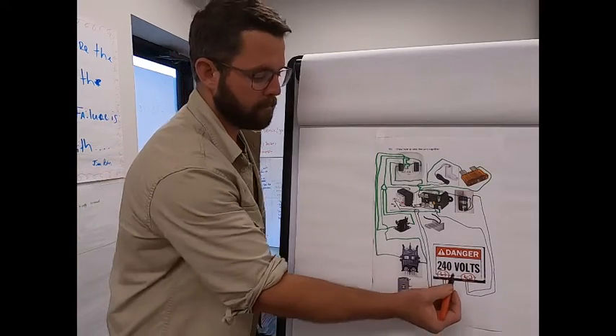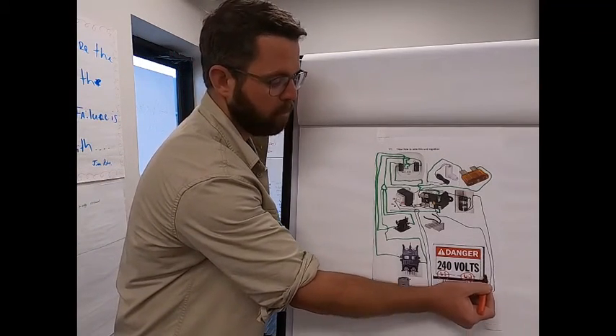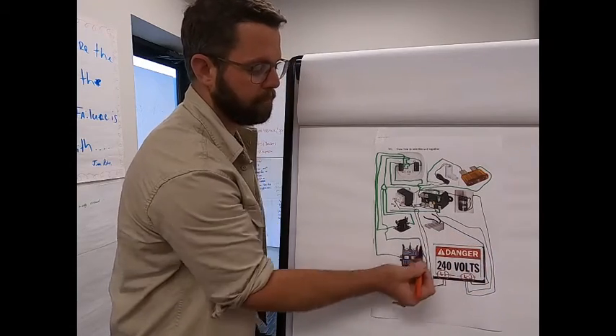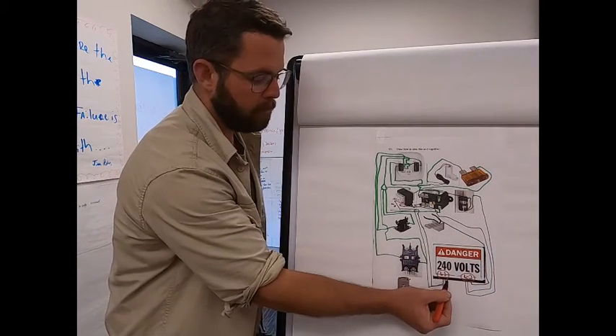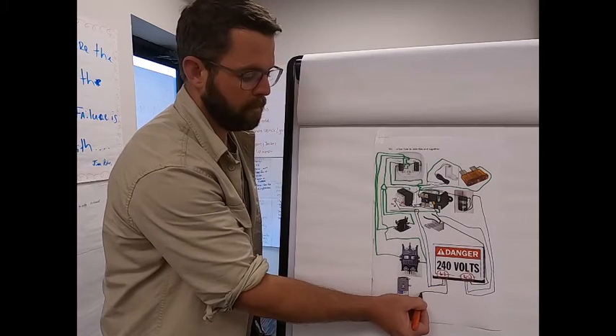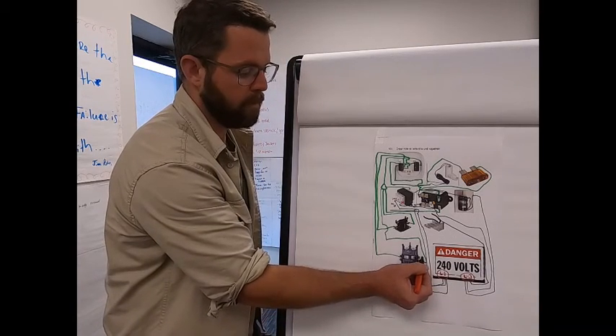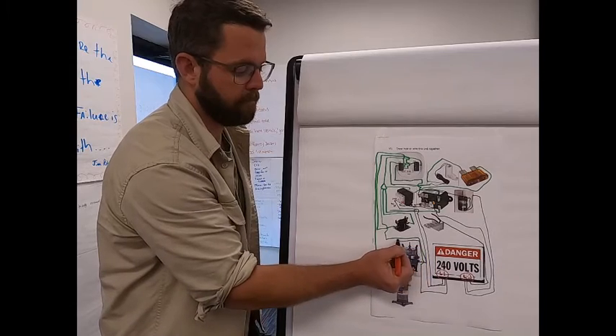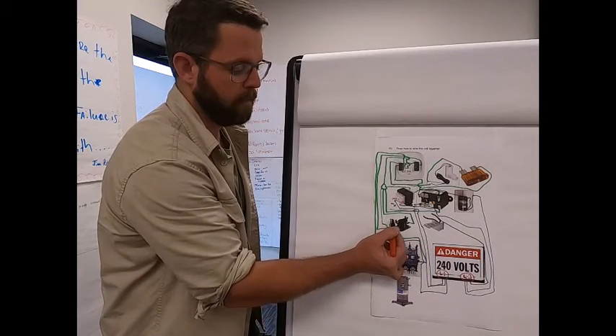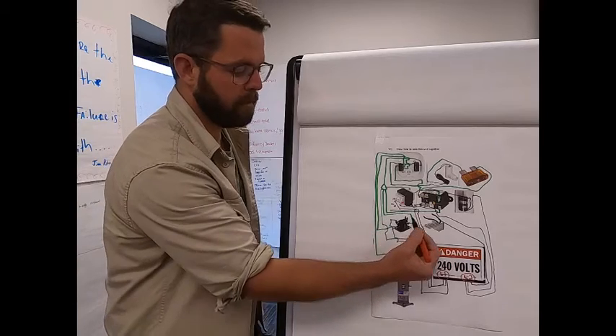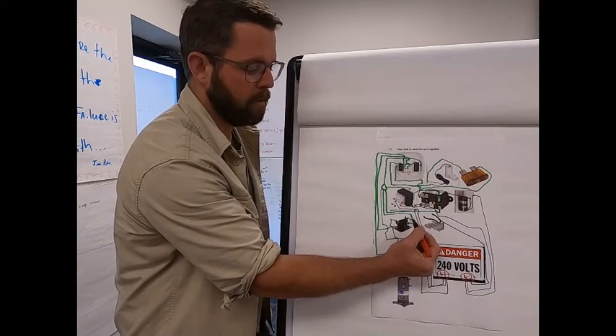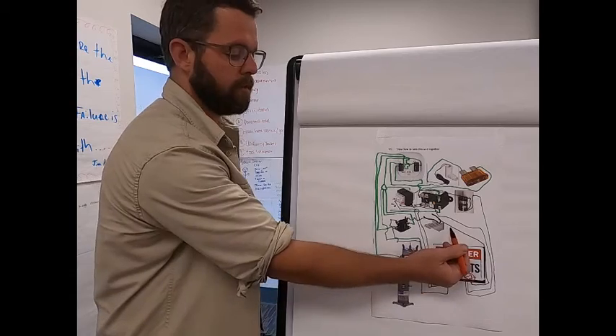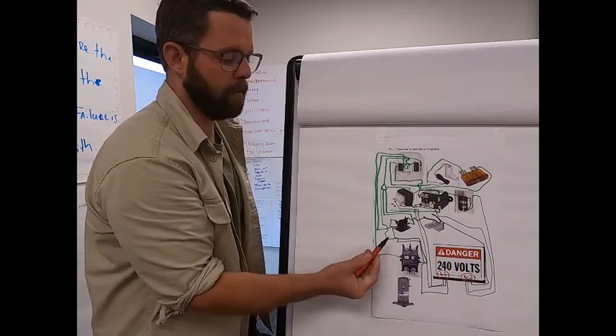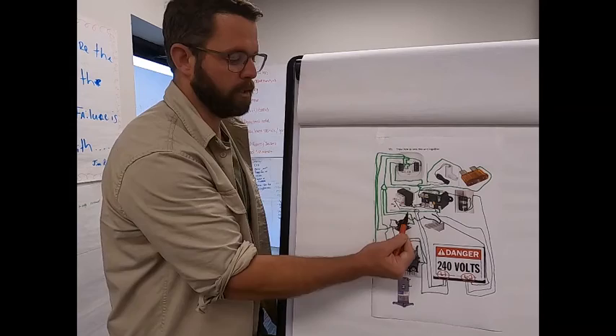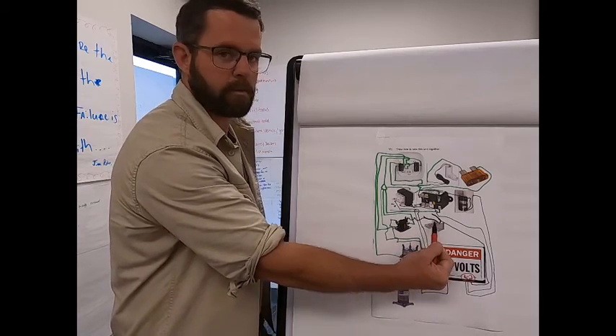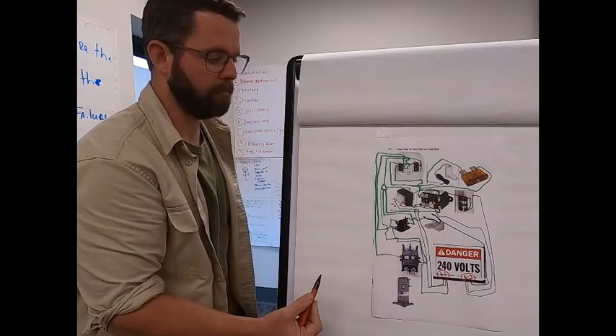Now our heat strips. One side of our heat strips will be constantly powered from L2. The other side will be powered by L1. But it has to run through the heat sequencer first. It will attach here to the heat sequencer. On the other side of the heat sequencer, we will go to the heat strips. That way, when our W calls from our thermostat, voltage can pass through and go to this heat coil.